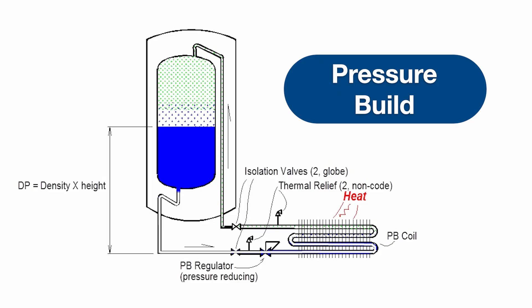When the pressure is low enough to open the PB regulator, weight of the liquid drives fluid out of the tank and through an ambient air heat exchanger, or PB coil. The PB coil adds heat to the liquid boiling it into a vapor. Liquid head continues to push the vapor into the top of the tank. The pressure building circuit thus raises the tank pressure until the pressure regulator automatically closes.